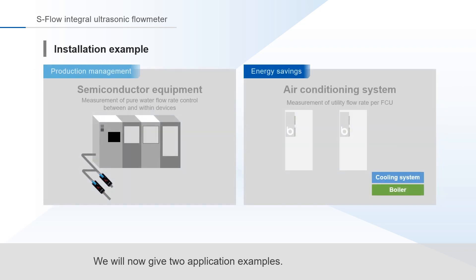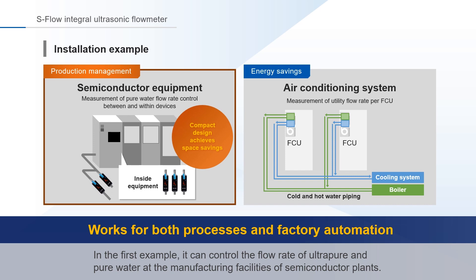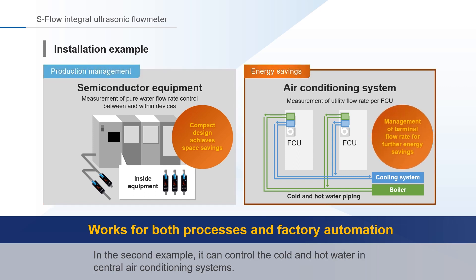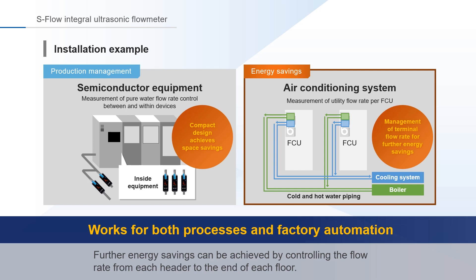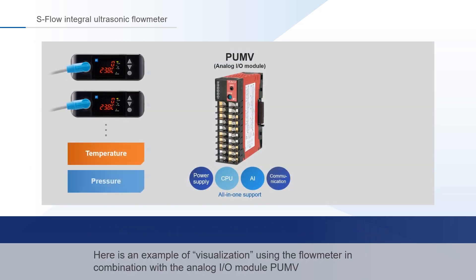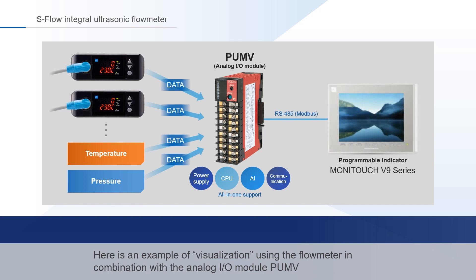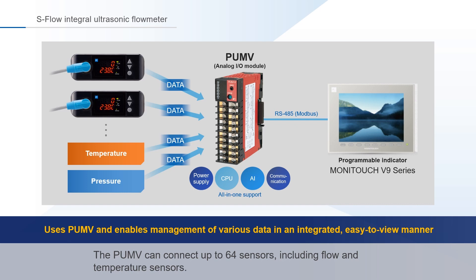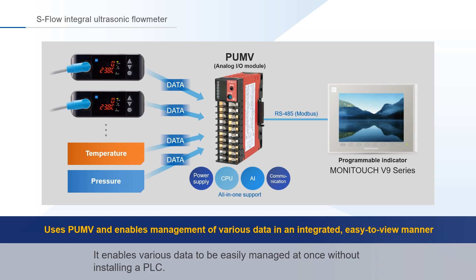We will now give two application examples. In the first example, it can control the flow rate of ultra-pure and pure water at the manufacturing facilities of semiconductor plants. Its compact structure enables installation at sites with dense piping and within equipment. In the second example, it can control the cold and hot water in central air conditioning systems. Further energy savings can be achieved by controlling the flow rate from each header to the end of each floor. Here is an example of visualization using the flow meter in combination with the analog I/O module PUMV and programmable indicator. The PUMV can connect up to 64 sensors, including flow and temperature sensors, and can be displayed on the programmable indicator using the built-in RS-485 communication module, enabling various data to be easily managed at once without installing a PLC.